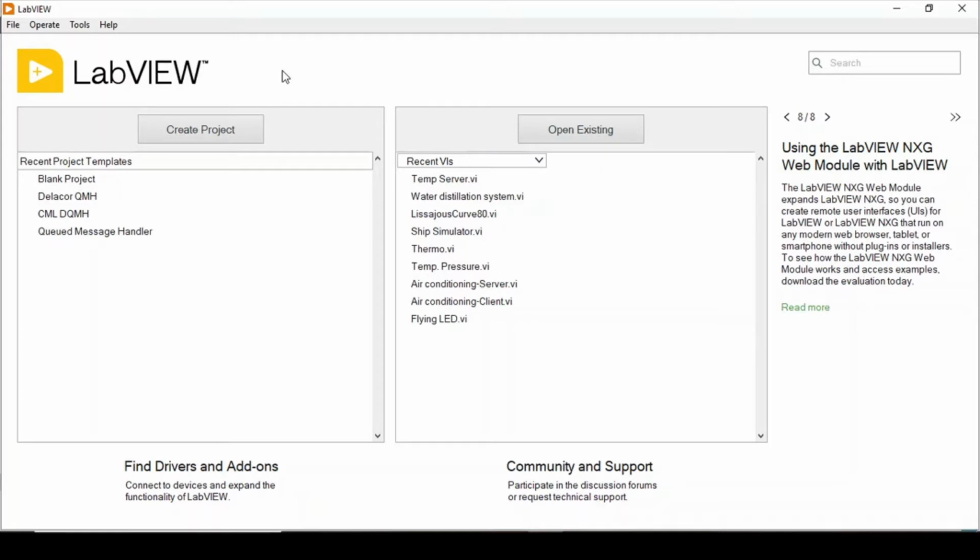We can create custom IO servers of two types: on the input change IO servers, and the second one is the periodic IO servers. We create periodic IO servers when we want to control the update rate of data items, and when we have a continuous update of the data items, for example temperatures. So today we will simulate temperature and see how we can create a custom based periodic IO server.